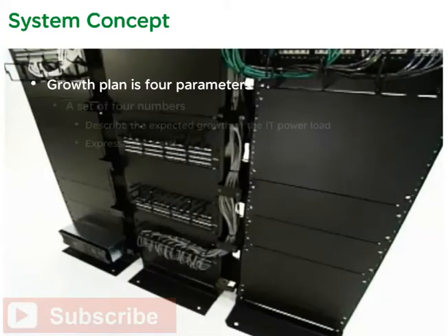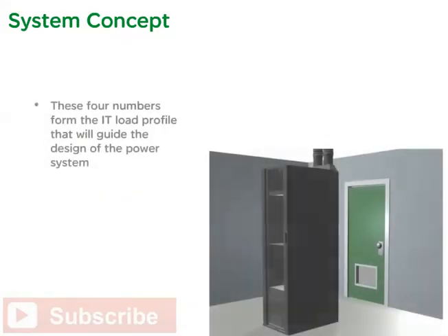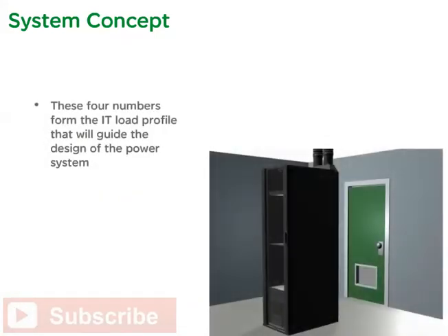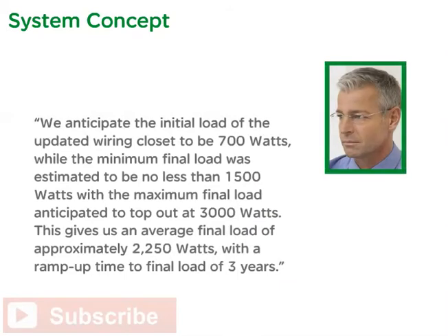The growth plan consists of four parameters — a set of four numbers that describe the expected growth of the IT power load expressed in watts. These four numbers form the IT load profile that will guide the design of the power system. Uncertainty about future growth is handled by providing both a maximum final load and a minimum final load, and assuming the option of a scalable system design that approaches the maximum value in increments over time. Crawford and Kelly discussed capacity and growth plan in great depth. They anticipated an initial load of 700 watts, a minimum final load of no less than 1,500 watts, with a maximum final load of 3,000 watts, giving an average final load of approximately 2,250 watts, with a ramp-up time to final load of three years.